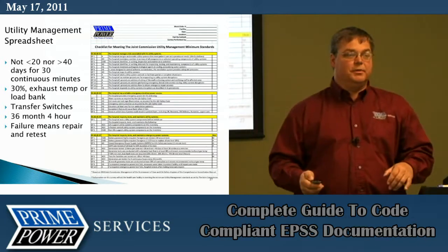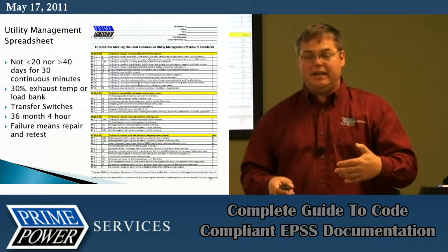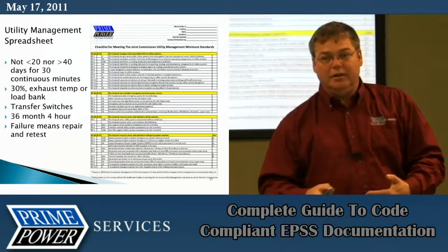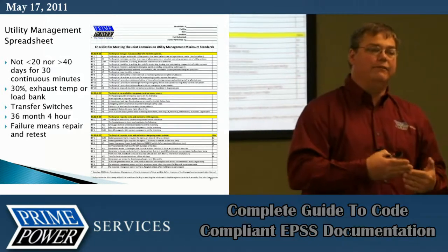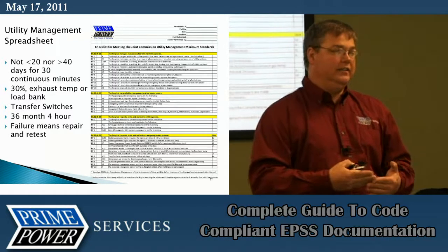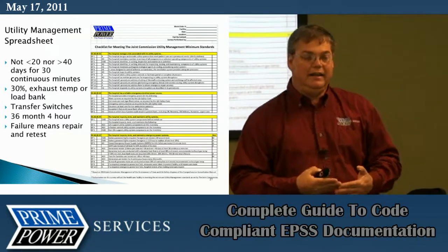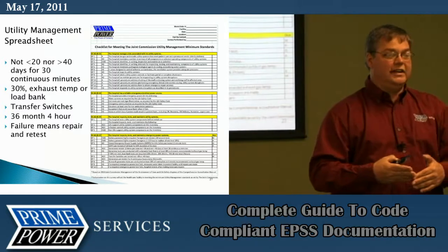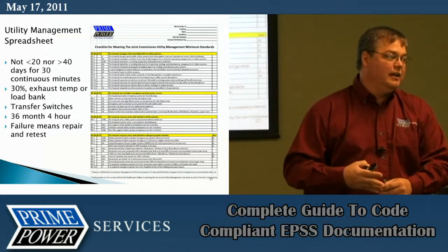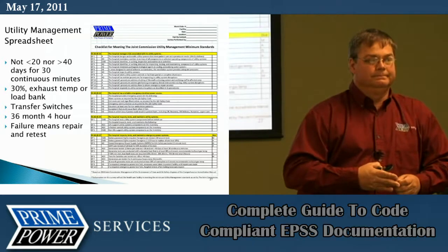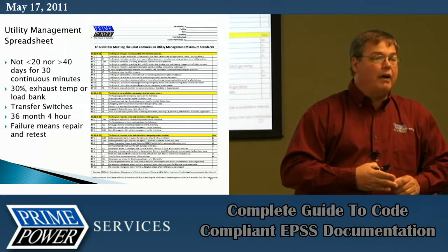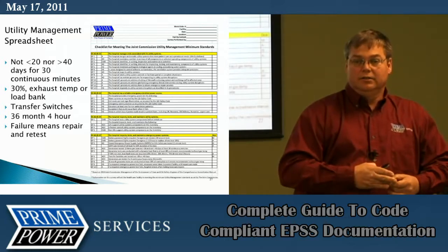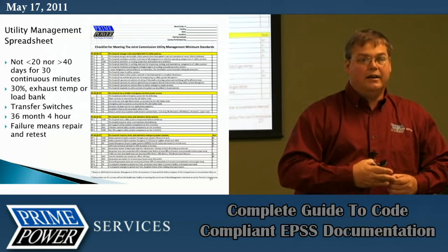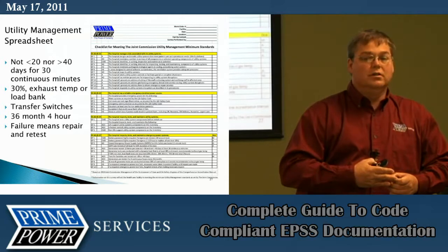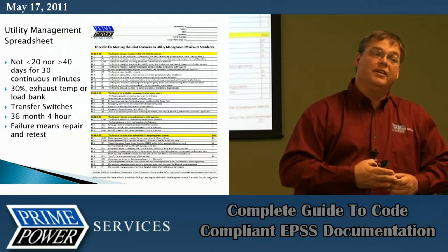All right. 36-month, 4-hour test we've talked about numerous times. Every 36 months, you have to test your generator at 4 hours. All right? It'll say at connected load in NFPA 110. All right? It'll say at 30% in Joint Commission. They want you to use that 30%. All right? So you're not required to use a load bank. For the non-healthcare, you just fire it up for whatever it's on. For you healthcare guys, you still got to meet the 30%.